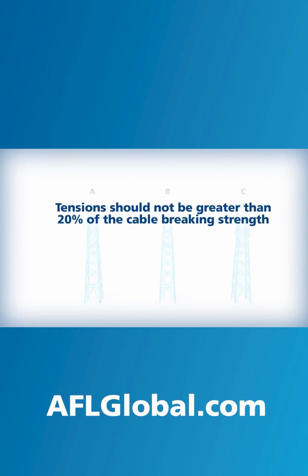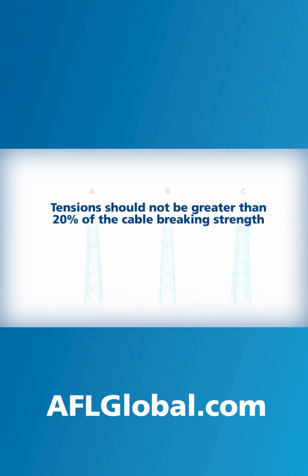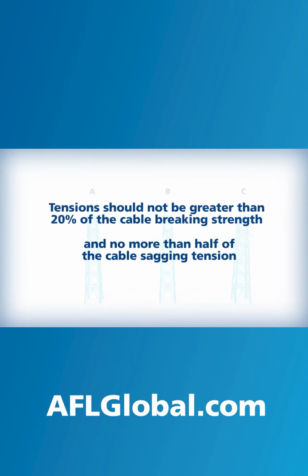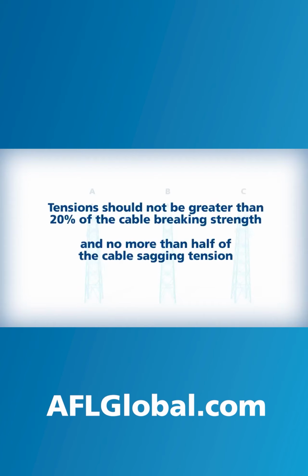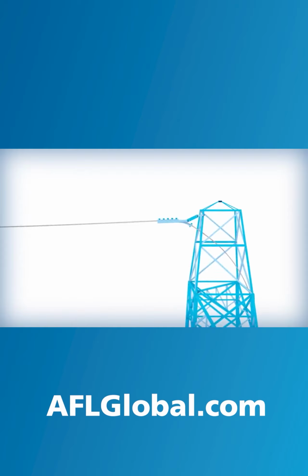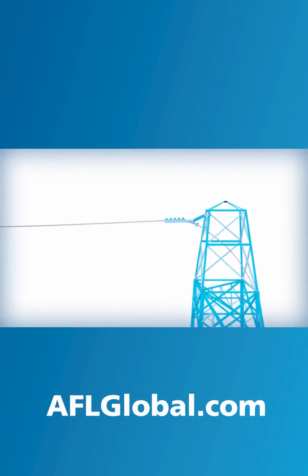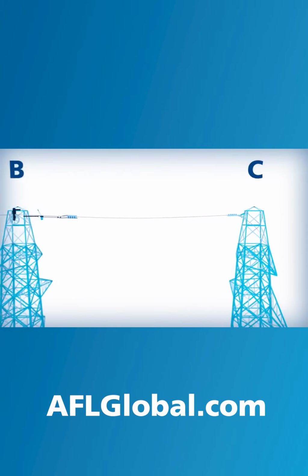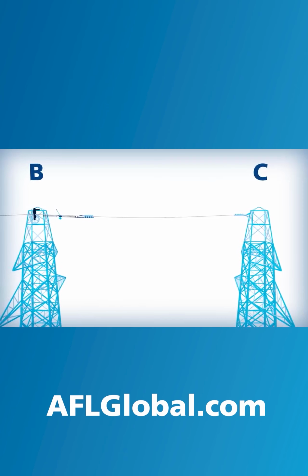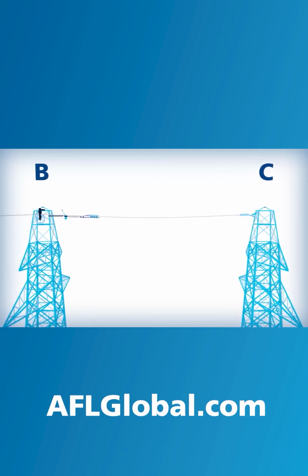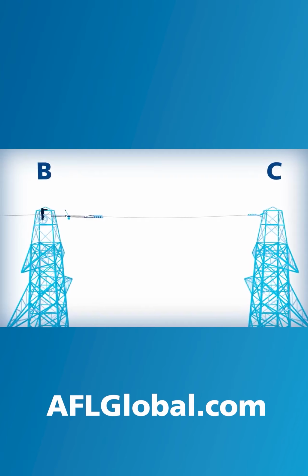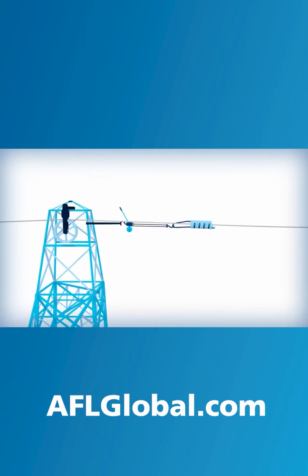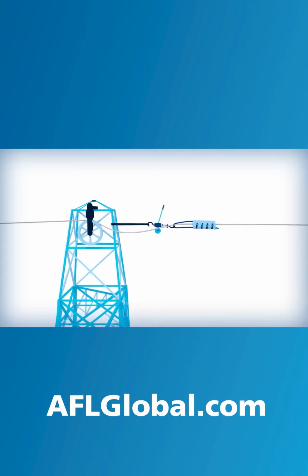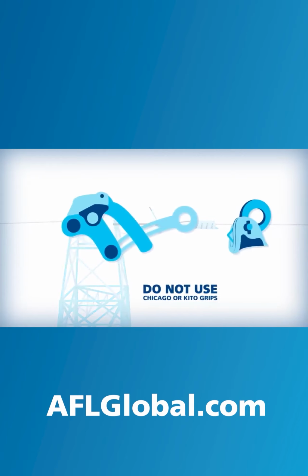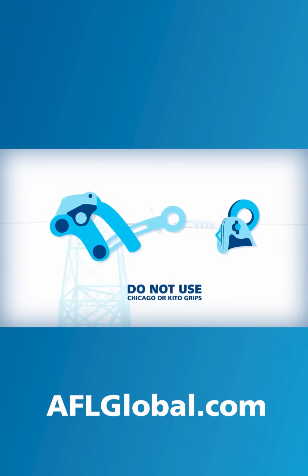Stringing tensions should not be greater than 20% of the rated breaking strength of the cable and no more than half of the sagging tension of the cable. To begin sagging the OPGW, a dead end should be placed on the last structure at the puller location. Sagging should be conducted on each dead end to dead end section, working back to the OPGW reel and tensioner location, and a come-along or pocketbook grip should be used to tension the cable. Chicago or Kito grips should not be used.